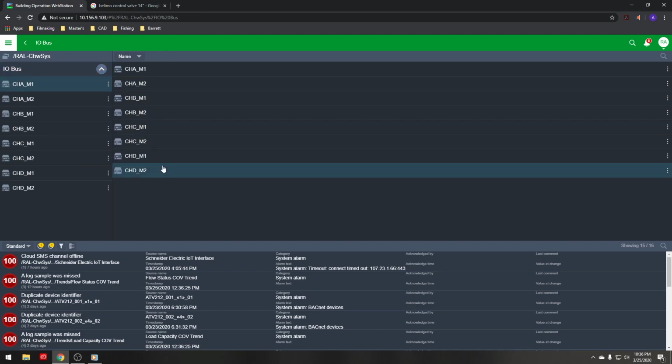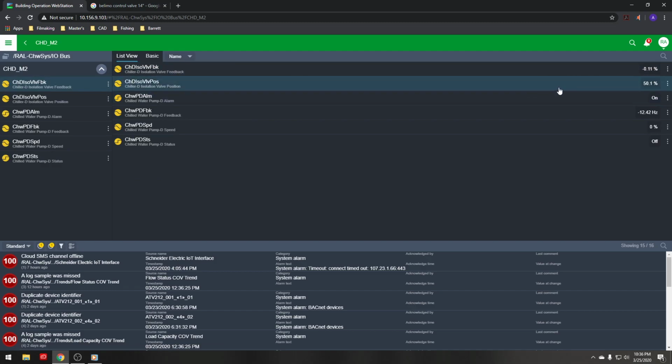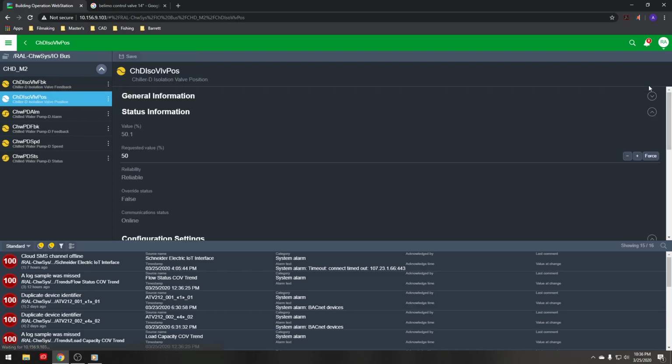And chiller D. So what state is it in? We know that the feedback valve is actually at 50%. That's kind of alarming. I had just said, hey, we don't want anything to be at that. I don't know if that's a... and there it is. It's a requested value. For whatever reason, that was told to be in that position. And there we go.